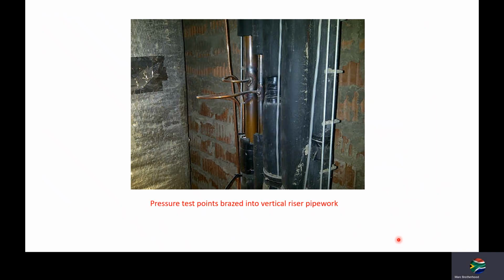Pressure testing. Here we can see that somebody has pressure test points that have just been brazed vertically into a vertical riser in a building. So the problem with this is when you braze on copper, it anneals the copper, or in other words, it makes it much softer. And it's going to affect the structural integrity of the pipework. There's a very high risk of pressure leaks ultimately and fractures in the pipework due to this practice. You never ever pressure test like this. Never.